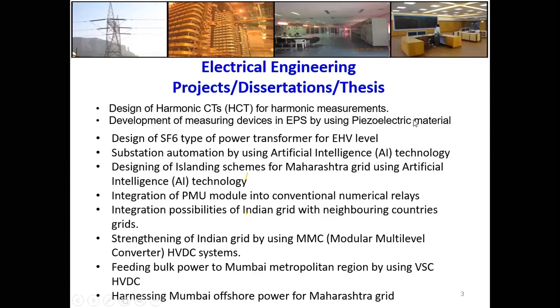Then for harmonic measurement, we have to use an analyzer, a harmonic analyzer, like portable devices. So why not go for direct installation of a harmonic CT? Harmonic CTs can be developed and installed in the substation itself, or at the distribution level, so that you can measure harmonics, since now we are talking about power quality. Measurement is the issue for harmonics, so you can design harmonic CTs, known as HCTs. This is also one of the areas you can work on.